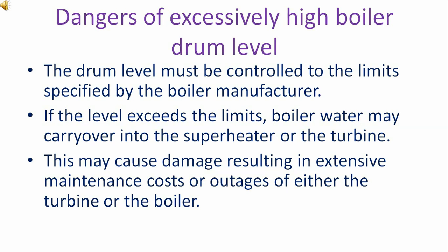The drum level must be controlled to the limits specified by the boiler manufacturer. If the level exceeds the limits, boiler water may carry over into the superheater or the turbine. This may cause damage resulting in extensive maintenance costs or outages of either the turbine or the boiler.